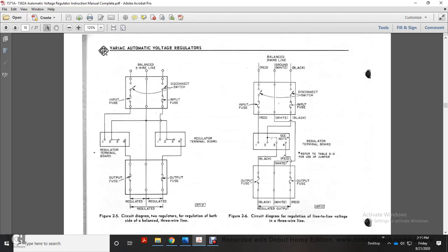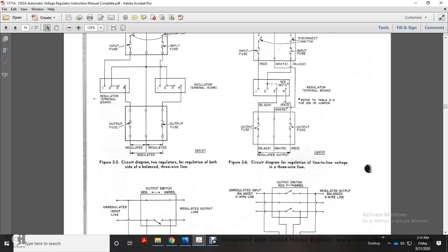Alright, Figure 2.5 shows a circuit diagram of two regulators for regulating both sides of the balanced 3-wire line. Balanced 3-wire line, disconnect switch, input fuses, regulator terminal board, output fuse, regulated output. Figure 2.6 shows the circuit diagram for regulation of line-to-line voltage of a 3-wire line. You have the balanced 3-wire line, red, ground, white, black. Disconnect switches, input fuses, red, white, black. Regulator terminal board, output fuse, black, white, red, regulated output.